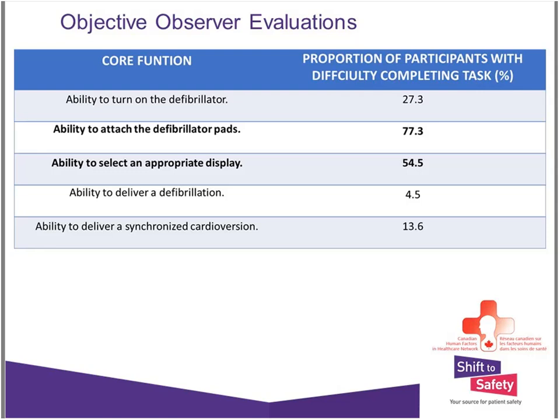The default of the defibrillator is that the cable is actually attached to a battery at the start. So the user has to disconnect from the battery and then apply either the pads or the paddles to the patient. Most people think the paddles are automatically attached to the defibrillator, and I've seen many, many times people try to deliver shocks with the paddles, and it's not even connected to the machine. And that's because of the default mode that the defibrillator is in.